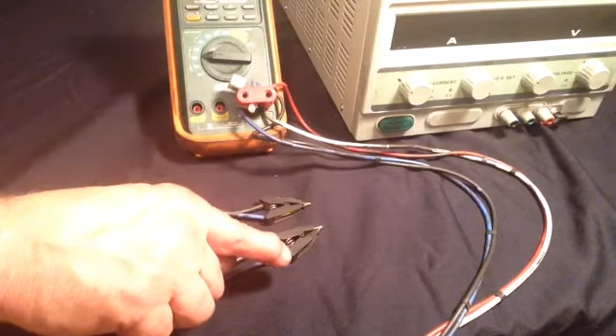These are called Kelvin clips, or 4-wire connections. They allow me to have separate connections for the power supply and the voltmeter when I'm testing a sample. You can see how, even though it looks like an alligator clip, because the two probes are insulated, we essentially have 2 separate connections. And the same for the other plug, so that gives us our 4 connections.